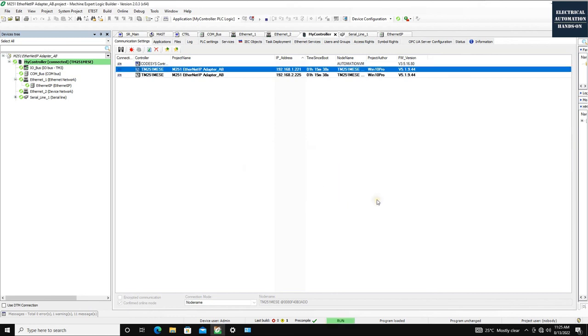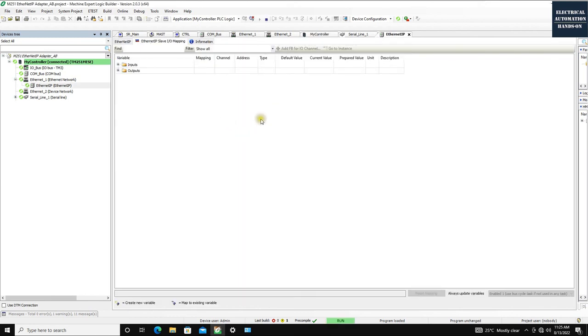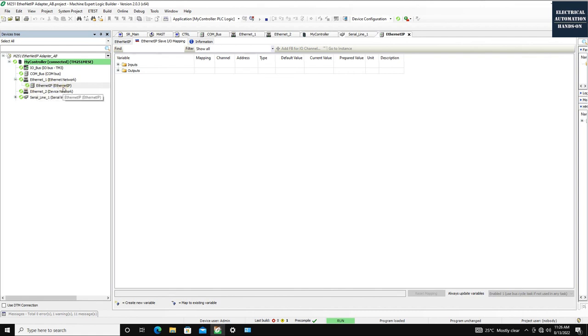After performing start, the controller is running and everything looks okay. But keep in mind: the green icon shown here doesn't mean the EtherNet/IP communication is set up and working correctly, because we haven't configured the Allen-Bradley scanner side yet. The icon just shows the device itself is running properly.